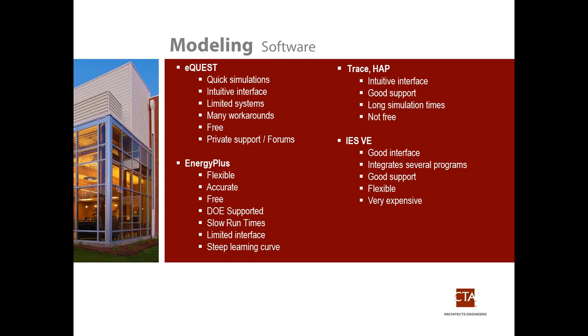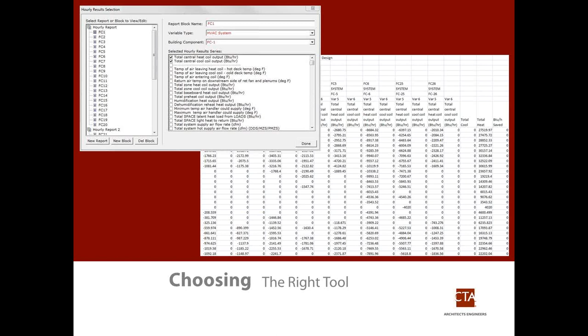Here's an example of when your energy model can't solve your problems. This is a VRV or VRF, variable refrigerant flow, system that does heat recovery—so if one room is in heating and another is in cooling, it can recover some of that heat. You go into eQuest, get your hourly heating and cooling loads, add them up, and get your totals. But it's real easy to spit these results out into a spreadsheet—don't be afraid to do that, and do the side calculations when you can't do it in the program.